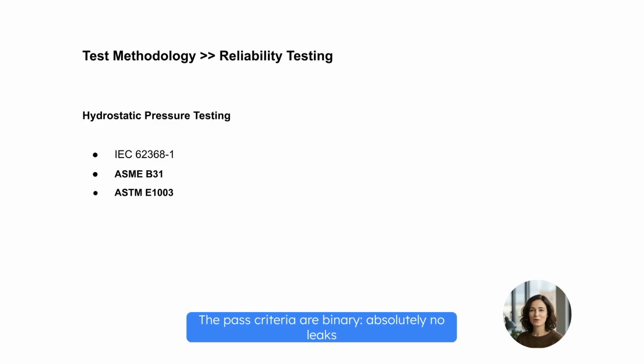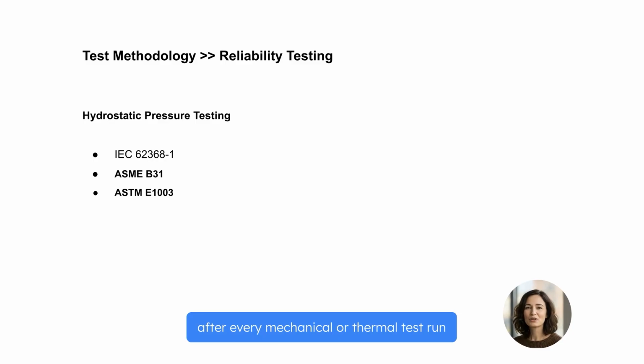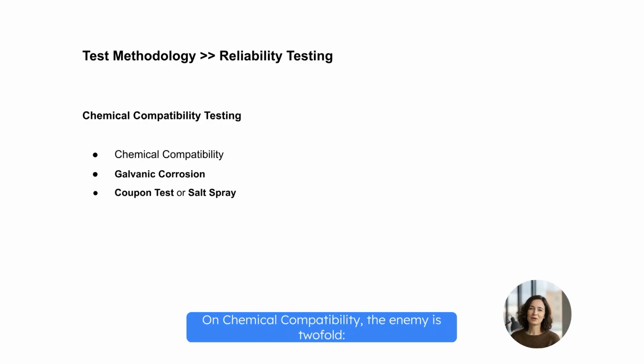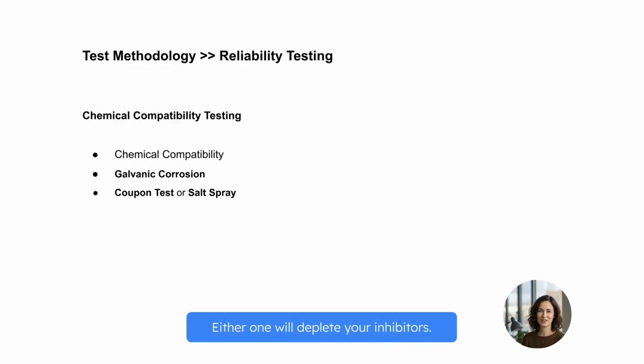The pass criteria are binary: absolutely no leaks and no physical deformation under pressure. But note the workflow. This isn't just a one-off check. You must perform a pressure verification per ASTM E1003 after every mechanical or thermal test run to ensure the loop integrity remains uncompromised. On chemical compatibility, the enemy is twofold: galvanic corrosion from dissimilar metals and leaching from reactive polymers. Either one will deplete your inhibitors.